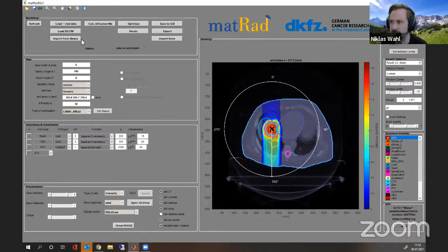So in the last 3 minutes, I want to show you another, let's say, problem of proton therapy, and I will switch the patient for that, which is basically now a head phantom. Okay, so it's not a real head, it's really a head that was pieced together from materials and built. It's very useful for quality assurance in treatment planning, so that you can pre-calculate plans, you can insert ionization chambers and so on. So you would really put this on the table and do some plan for it and irradiate it and measure if the machine is doing what it should be doing.